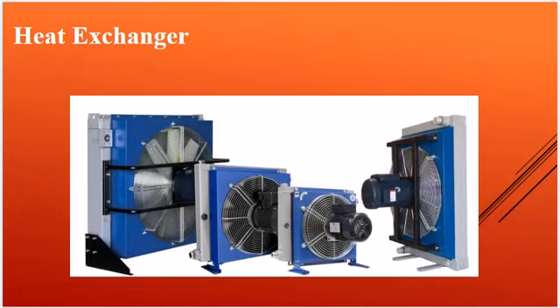Heat exchanger. A heat exchanger in fan systems is a device that facilitates the transfer of heat between two mediums, such as air, water, or refrigerants, without mixing them. In fan systems, heat exchangers are commonly used to condition air by heating or cooling it before it is distributed through ventilation ducts. For example, in HVAC systems, a fan pushes air over a heat exchanger coil containing hot or cold fluid, allowing the air to absorb or release heat.